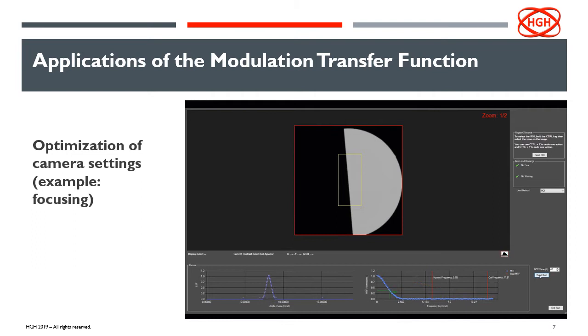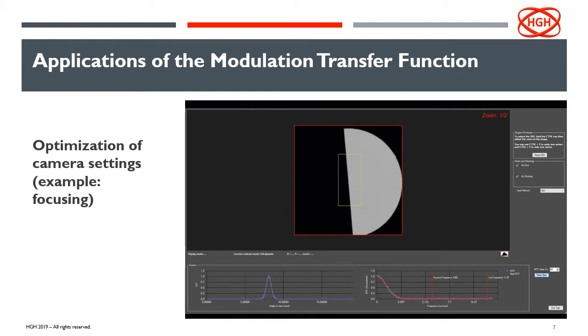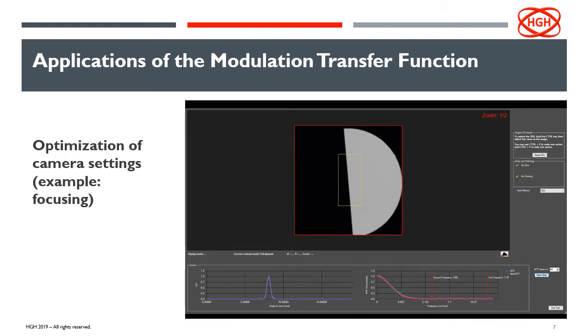Here we have an example of an image of a slanted knife edge on a camera. As we can see, if the camera is not focused, we have blur on this edge, which is represented by the blue MTF curve — a degraded curve with low MTF values. By optimizing this MTF curve, meaning setting the camera so that the MTF is as high as possible for all frequencies, we are able to set the focus and confirm the camera is well focused.